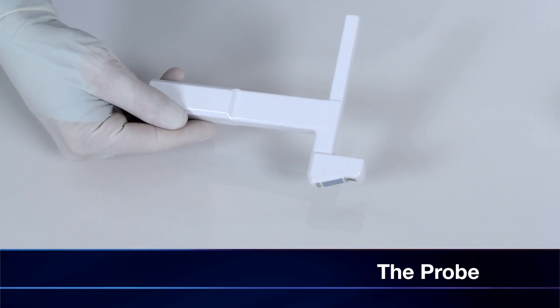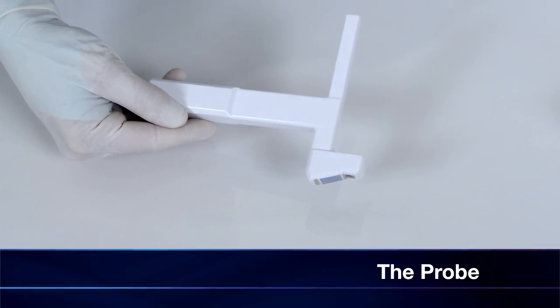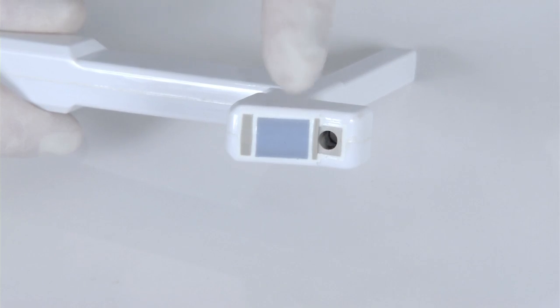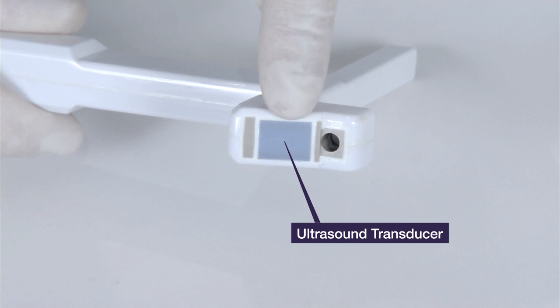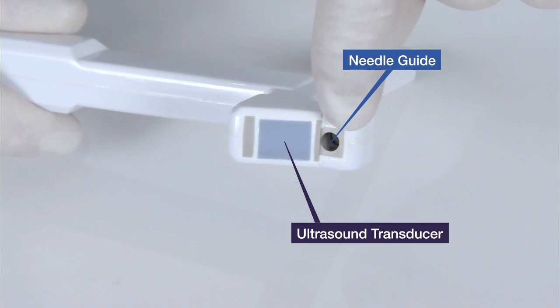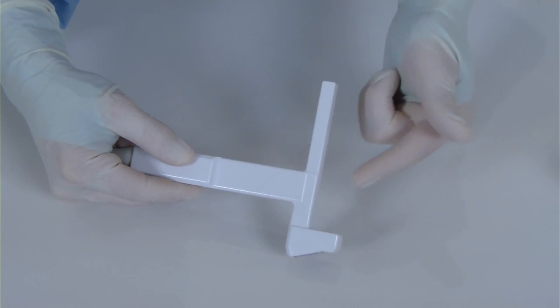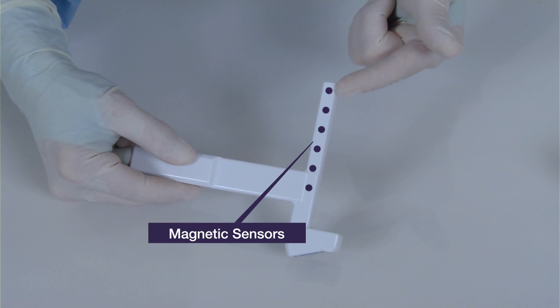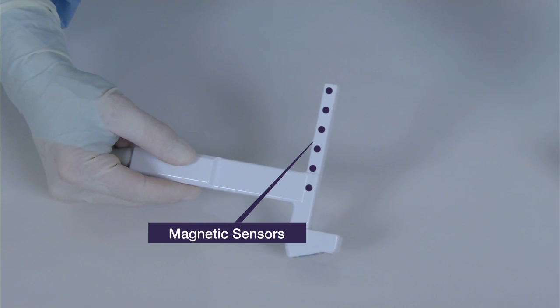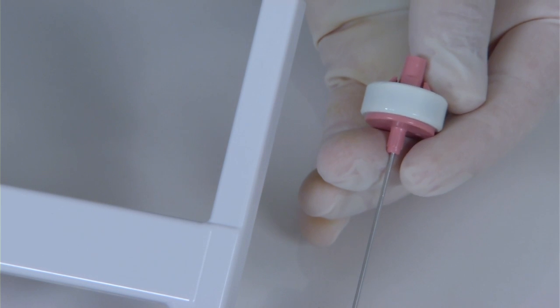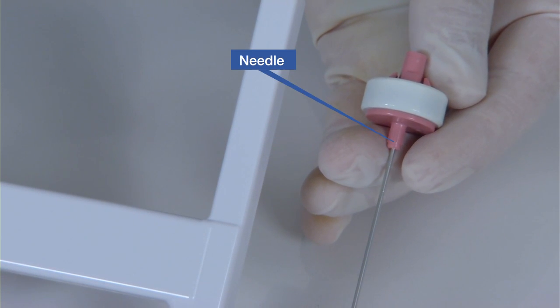The probe has an ergonomic design that gives it a look different than a typical probe. It has a standard ultrasound transducer with a needle guide integrated into the probe body. Built into the vertical post is an array of magnetic sensors that facilitates needle visualization. These sensors precisely sense the position of a magnet mounted on the hub of the needle included in an AxoTrack sterile procedure kit.